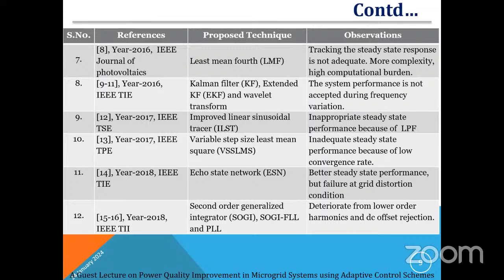In some conditions the dynamic performance is fine, okay. But in other conditions like DC offset, we have to maintain the DC offset at 0. If we are not maintaining the DC offset at 0, what will happen? End users who have connected PCs, laptops and other sensitive equipment will see failures, or sometimes the equipment will be damaged. So we also have to take care of that in this research area. These control schemes fail, particularly in DC offset rejection.